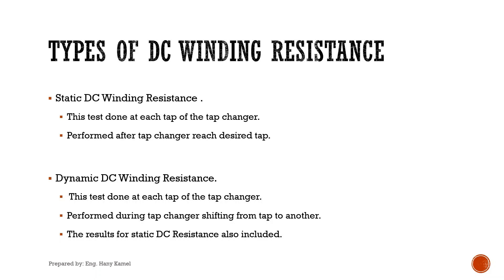Winding DC resistance test has two types: static and dynamic DC resistance. For static DC winding resistance, it is performed after the tap changer reaches each desired tap. For dynamic DC winding resistance, it is performed during tap changer shifting from one tap to another. Both tests are done at each tap of the tap changer. The results for static DC resistance will be included during the dynamic test, but if you perform only the static resistance, the dynamic values will not be measured.